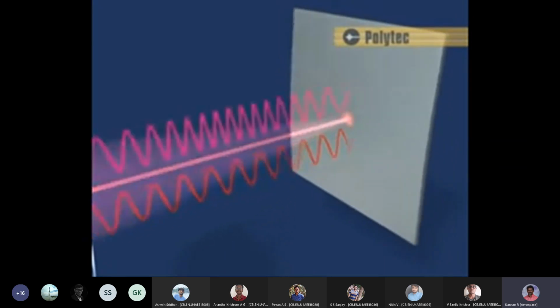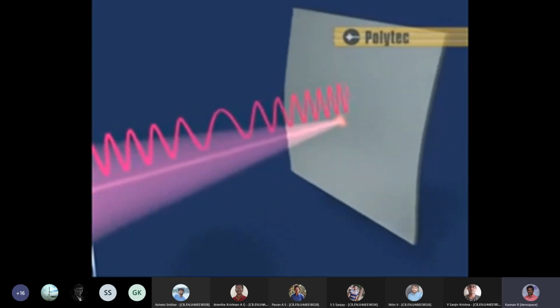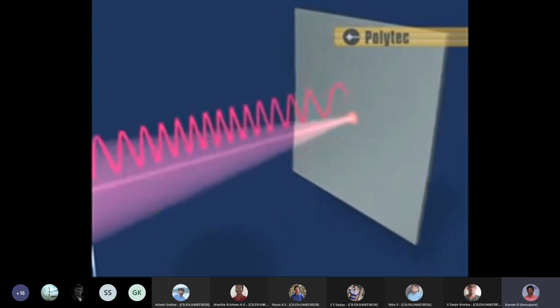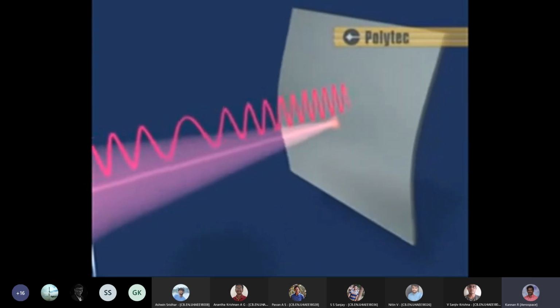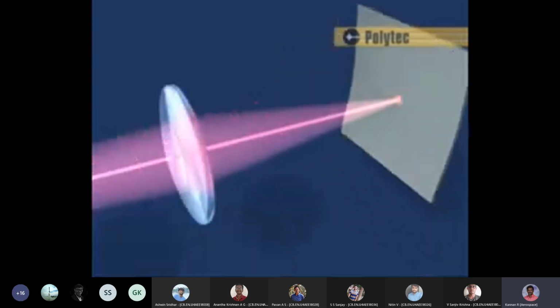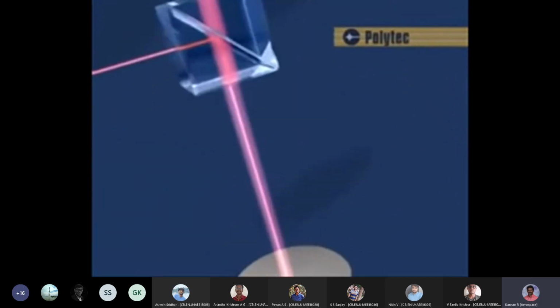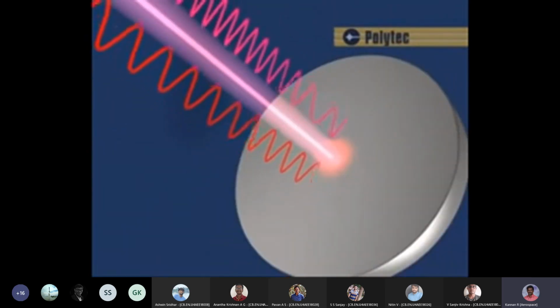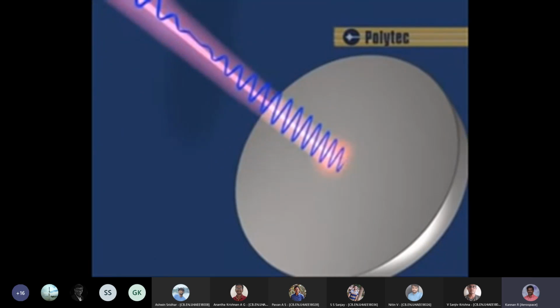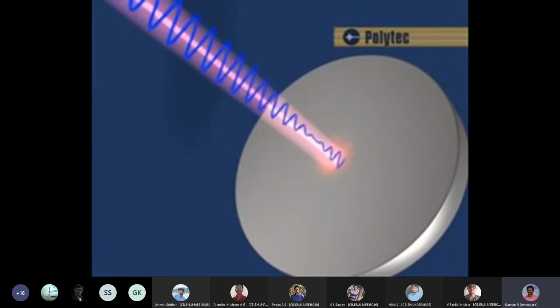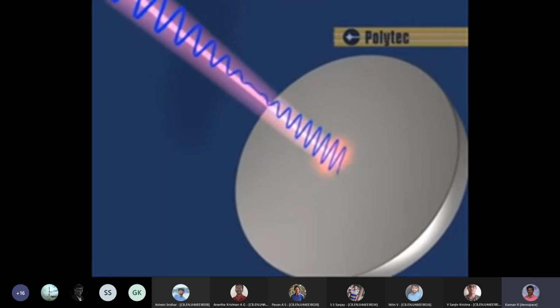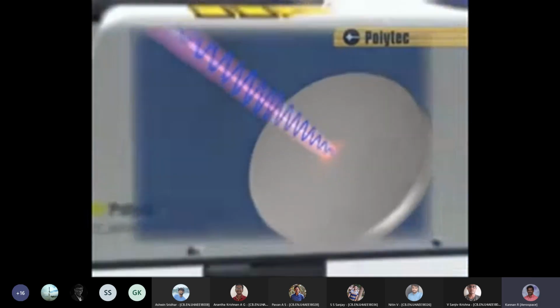Depending on the velocity and displacement, the backscattered light is changed in frequency and phase. The characteristics of the motion are completely contained in the backscattered light. The superposition of this light with the reference beam creates a modulated detector output signal, revealing the Doppler shift in frequency. Signal processing and analysis provides the vibrational velocity and displacement of the test object.